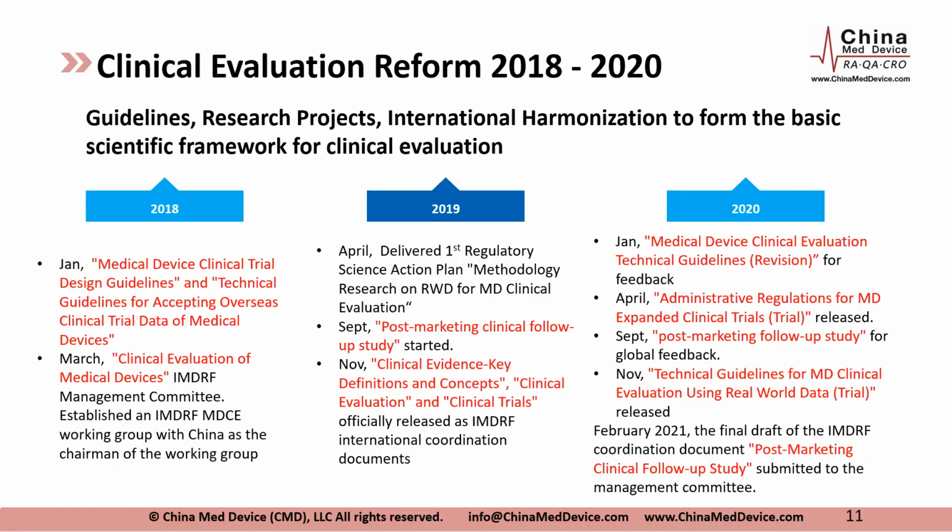Since 2018, 2019 and 2020, NMPA issued a series of clinical evaluation related guidance and documents. It's really important to note, for both China regulatory people and overseas people, that clinical evaluation, when it was first introduced in 2014 as a concept, meant pretty much everything was a clinical trial if you weren't on the exempt list and had no predicate device. If you needed a predicate device, back then it was very rigid. You needed authorization.